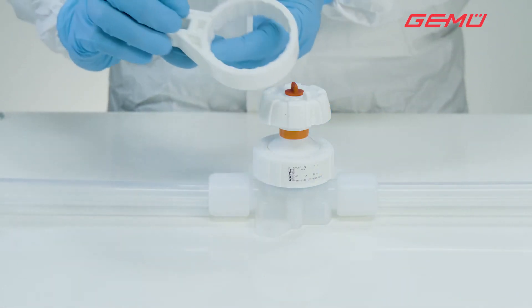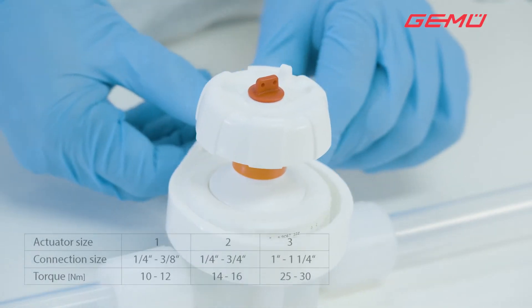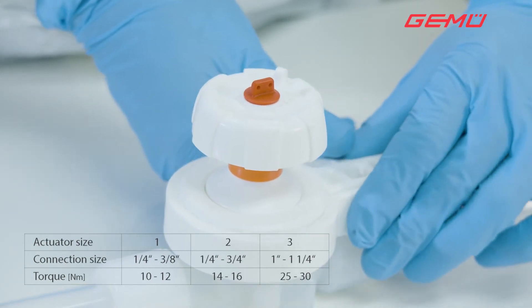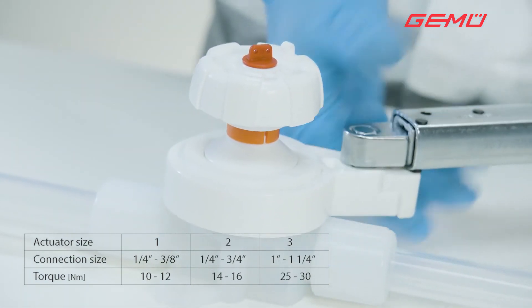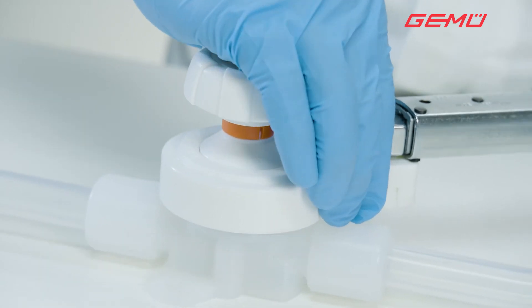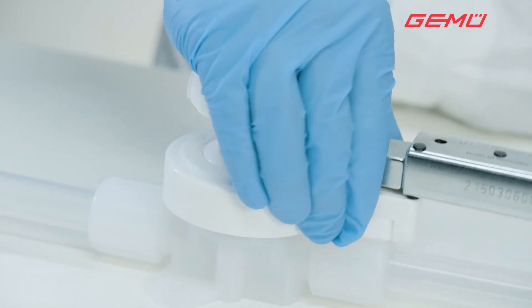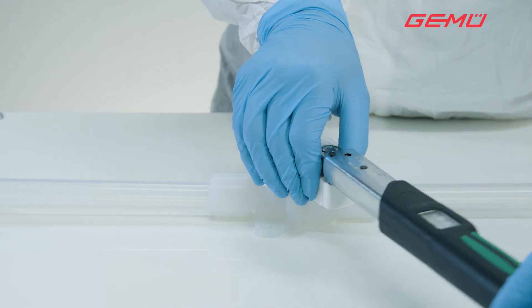Position the GEMU Service tool in the correct position on the central nut and attach the torque wrench in the extension for the service tool handle. Failure to do so will result in an incorrect torque. Tighten the central nut to the specified torque.